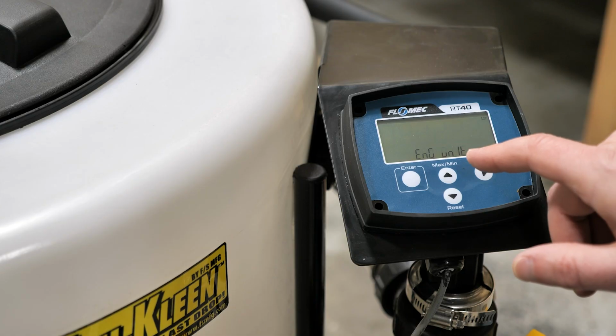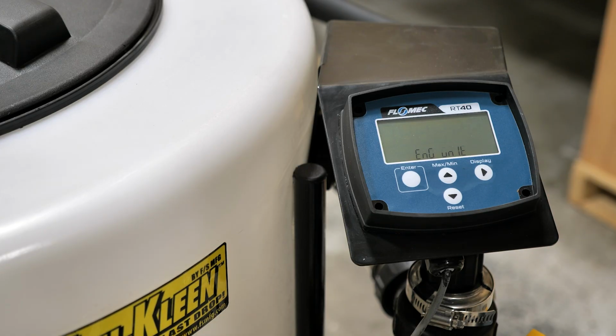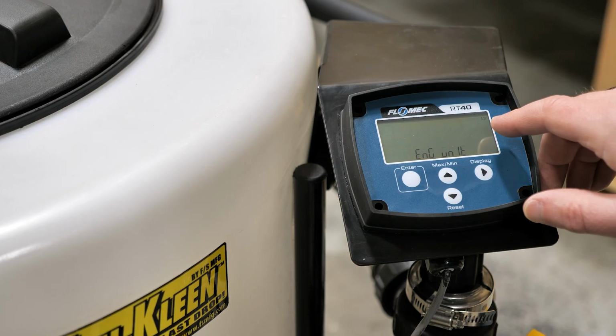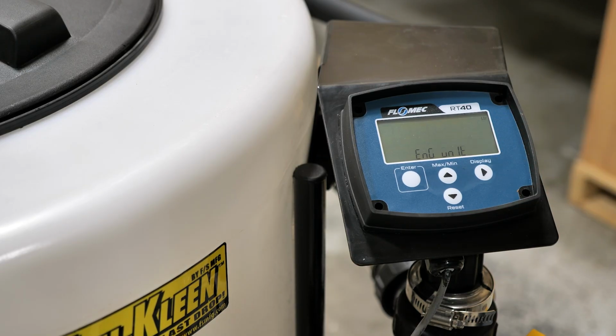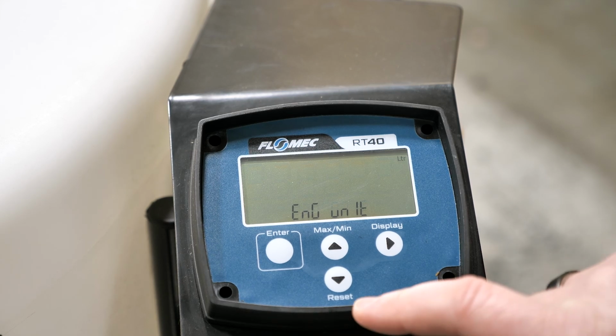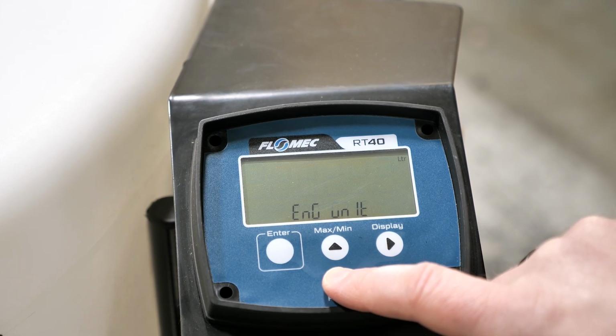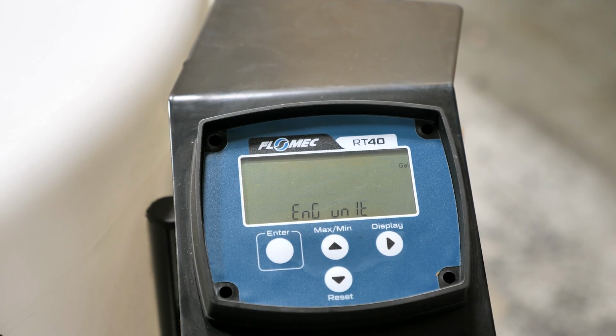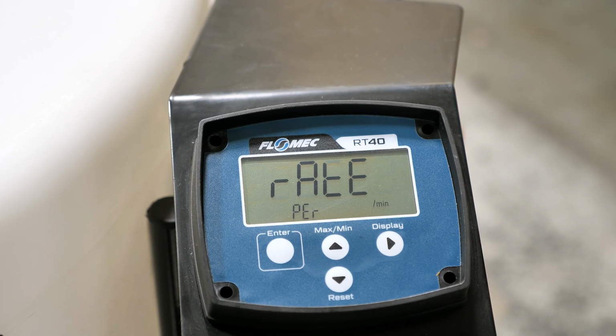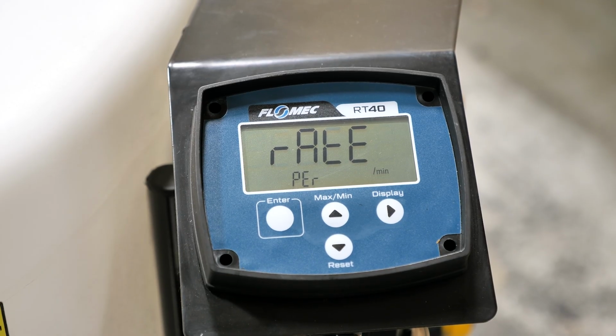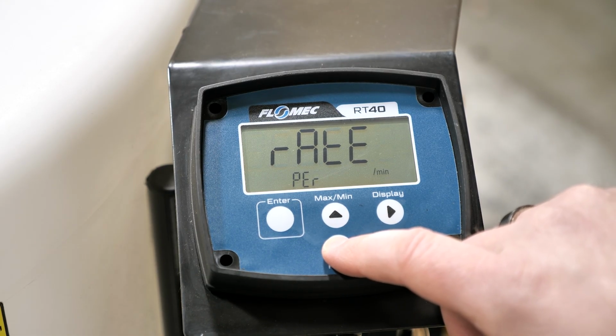Next setting is the engineering units. It is usually by default in liters. You can see it over here kind of blinking in the right corner, and we are going to change them over to gallons. Generally speaking, everybody is using gallons of liquid. So we'll change that over to gallons. We will hit enter, and now it is saved as gallons. This is the rate per time period, and it is defaulted as the rate, which is for us gallons now. So it's going to be gallons per minute. We're just going to leave that as per minute.